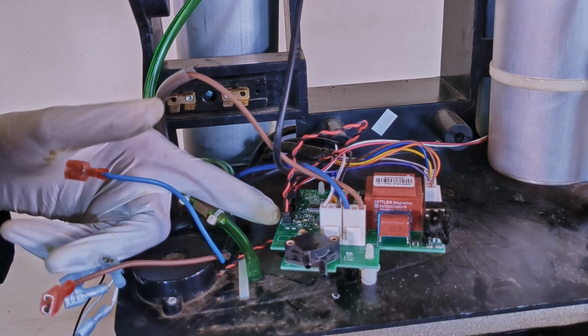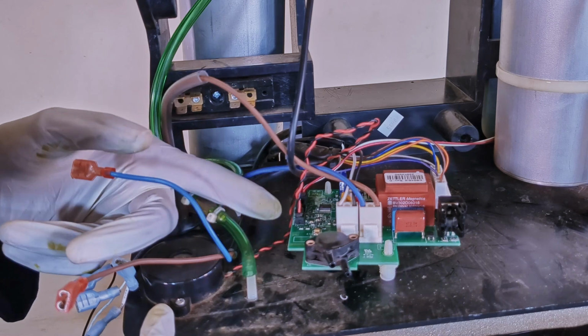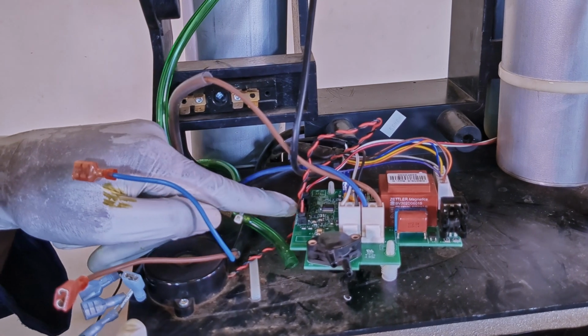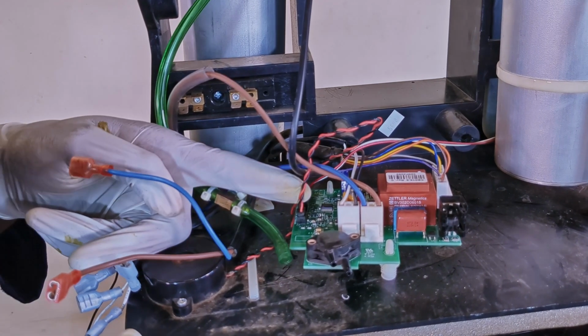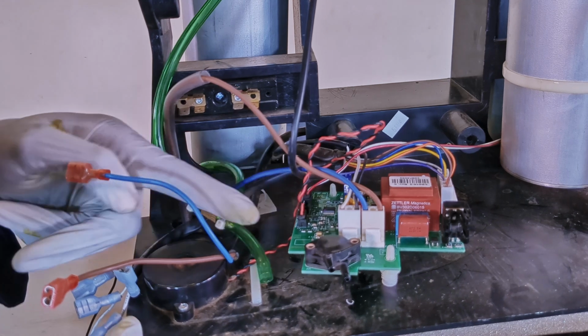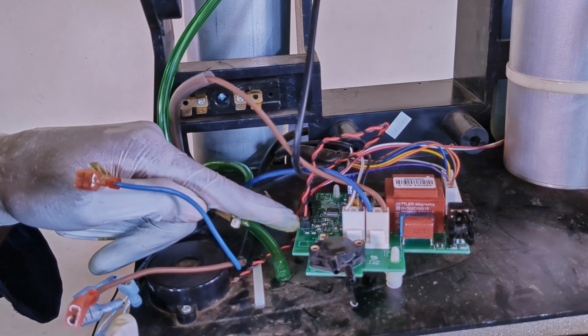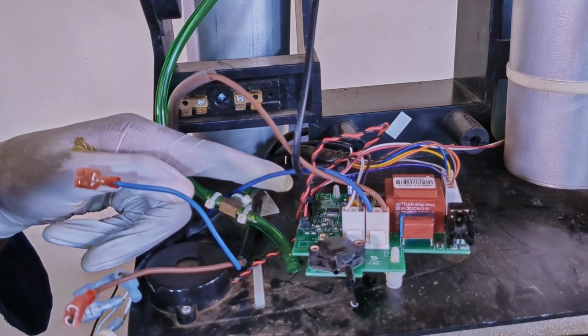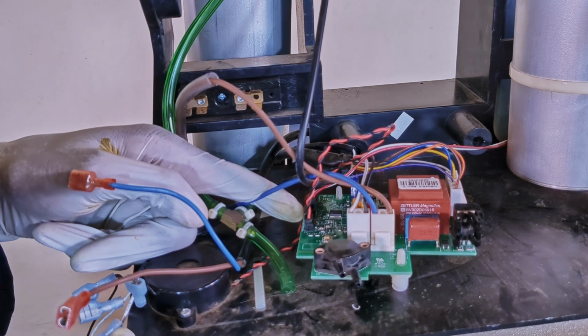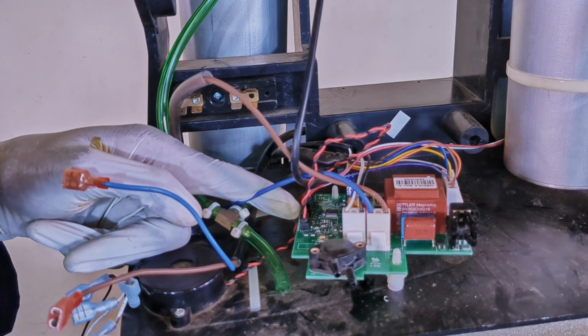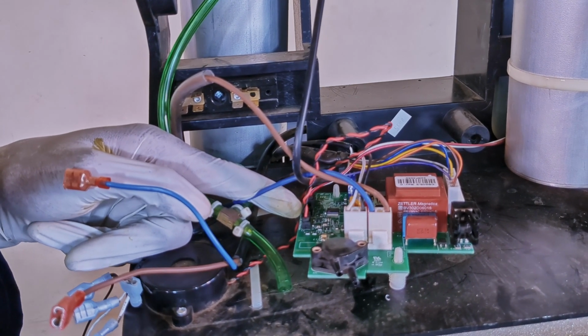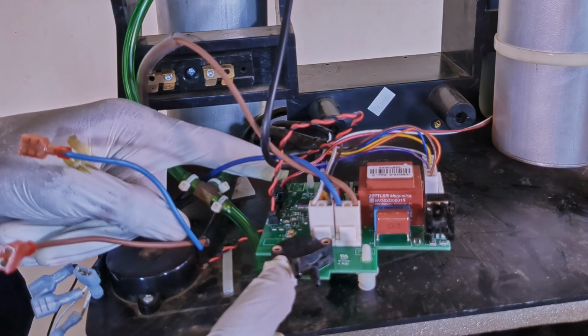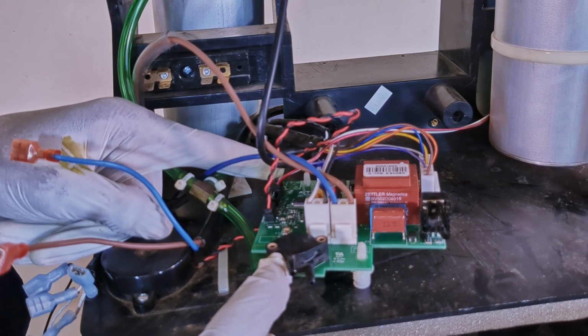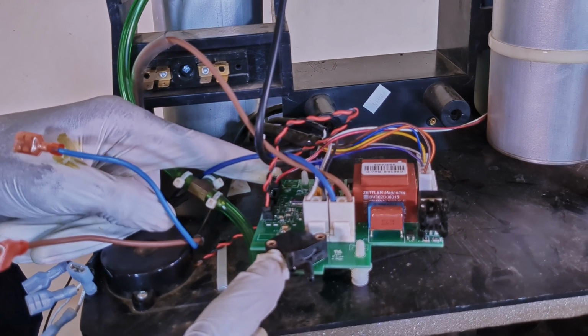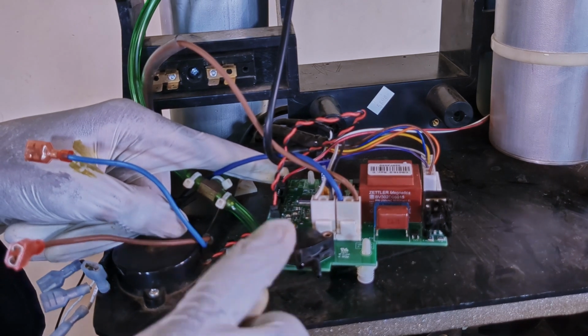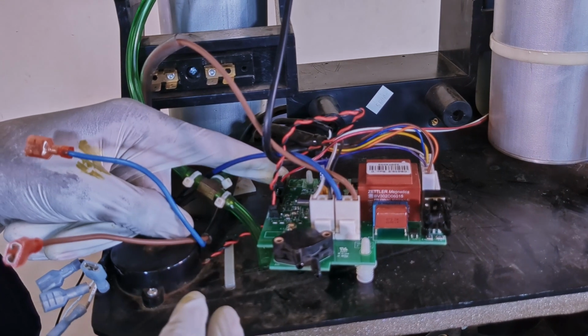On this side, on the DC output, we have 3 connection points. The connection point over here is for the buzzer. It is actually used to supply DC to the buzzer. In the middle here is where we connect the cable supplying power to the 3 indicator lights. And lastly, this connection point here is for the oxygen monitor circuit board. So it is used to power the oxygen monitor circuit board.